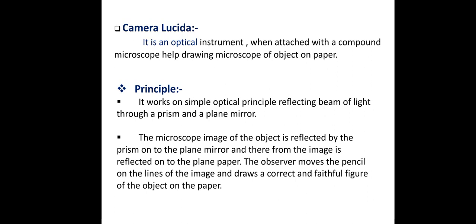Camera Lucida is an optical instrument which, when attached with the compound microscope, helps in drawing the microscope image of an object on the paper. It works on a simple optical principle: reflecting a beam of light through a prism and a plane mirror. The microscope image of the object is reflected by the prism onto the plane mirror and then onto the drawing paper. The observer moves the pencil along the line of the image and draws a correct and faithful figure of the object on the paper.